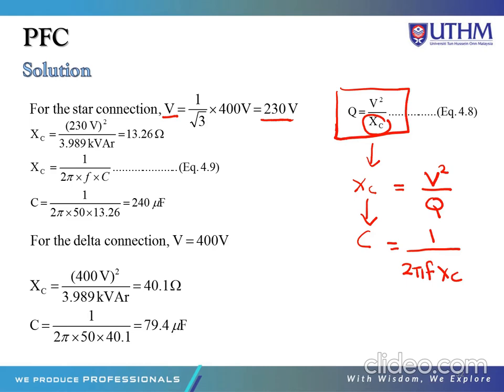Putting all the values here, we get the value of XC. Q represents the reactive power, the kVAr value. So we can get the value of XC, and then from XC we can get the value of C. This is the capacitance value that can improve the power factor from 0.763 to 0.9. For delta connection, V single phase is equal to V three phase. So just put this voltage value in the formula and we get the XC, and then we calculate the C.